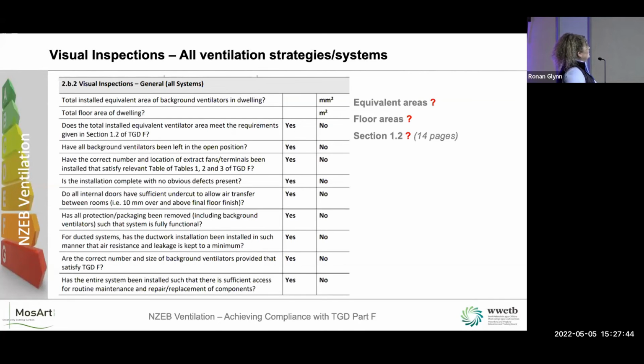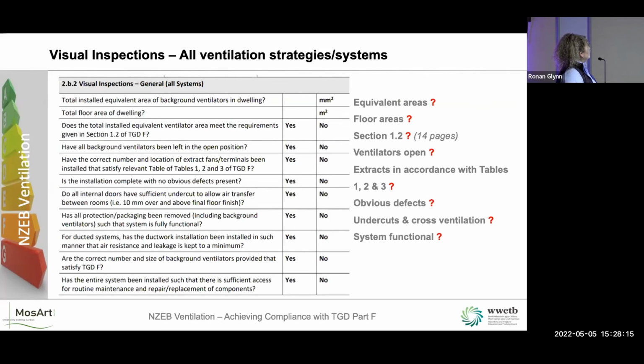Have the background ventilators been left in the open position? Like, you know, mostly they are closed. That little slot is closed off on it. At best, at worst, it's been taken off and there's a cushion or something in it. Are the extracts in accordance with the tables? Okay, so you need to go back to your tables 1, 2, and 3 there and find out. Is the installation complete with no obvious defects present? Yes or no, simple. Do the internal doors have the undercuts to allow cross ventilation? Is the system functional? Does anybody turn it on and actually see if it's working?